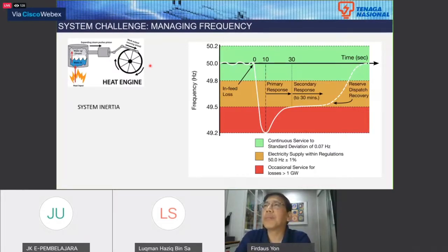I want to introduce you to the concept of system inertia by looking at the frequency response. When we have a disturbance, a fault—for example, if our transmission line snaps and drops to the ground—part of the system becomes earthed. You then have a fault current going through, so the system draws a lot of current for a period of time. Because of that extra load, it slows down the heat engine, and our rotating machines will slow down because of the extra load.